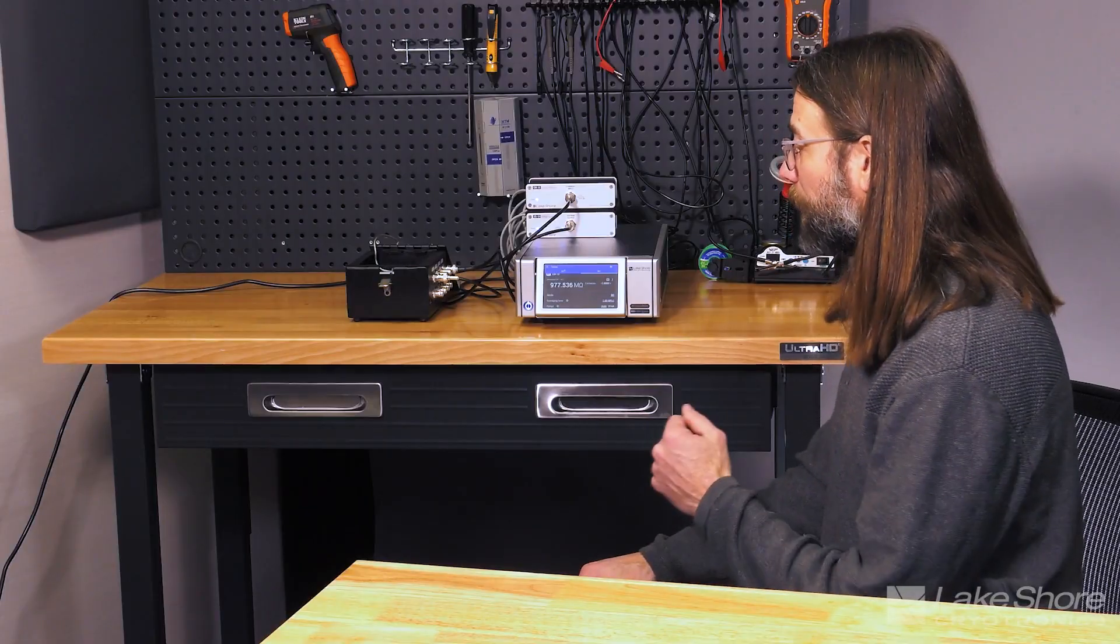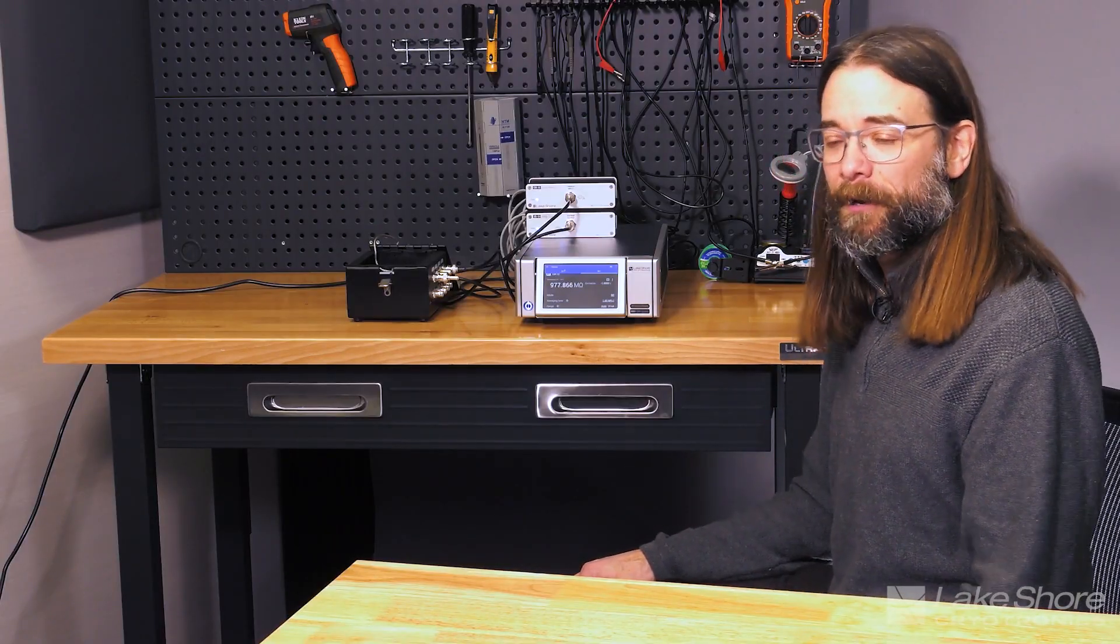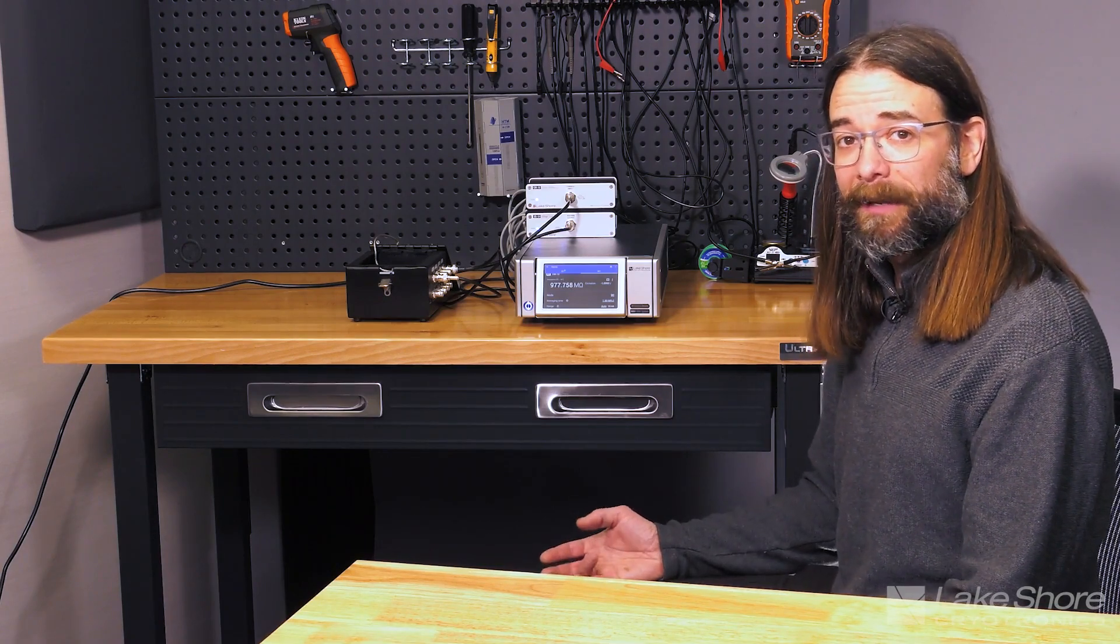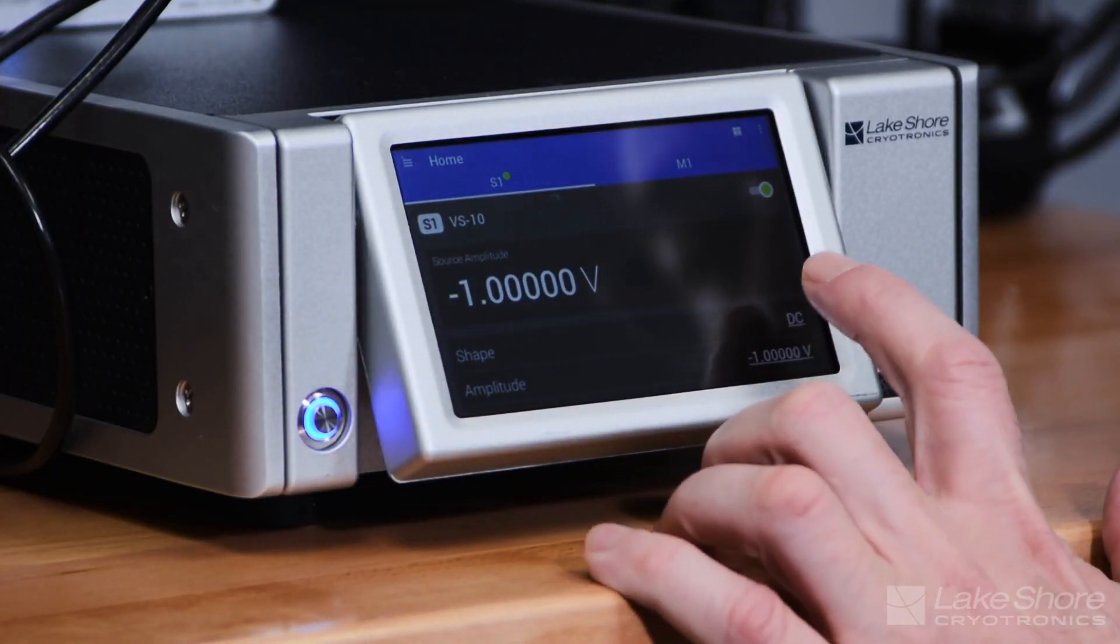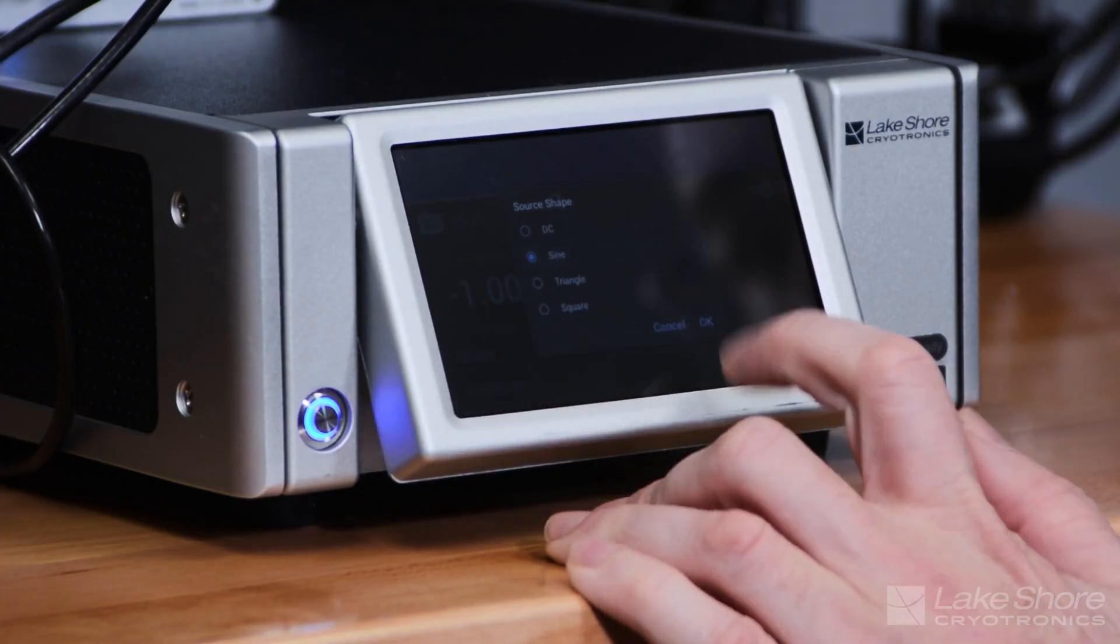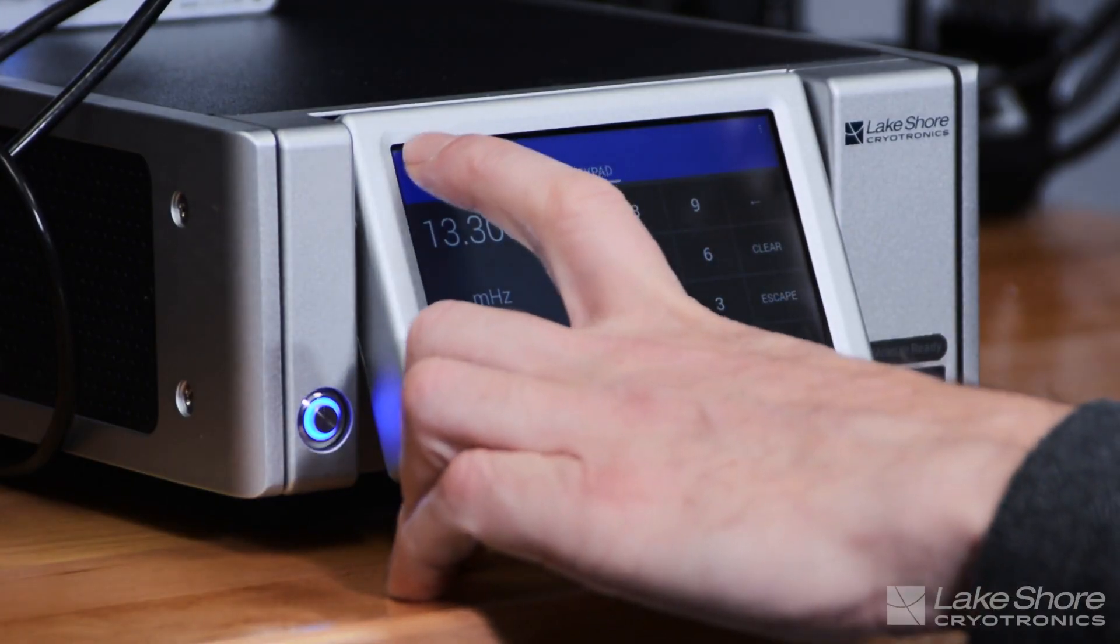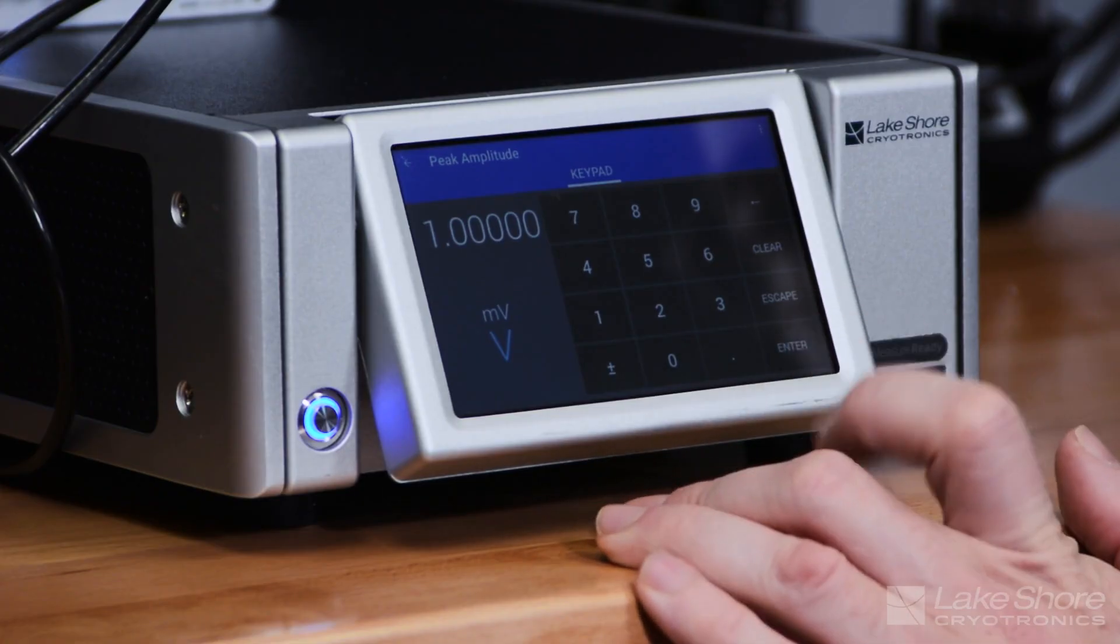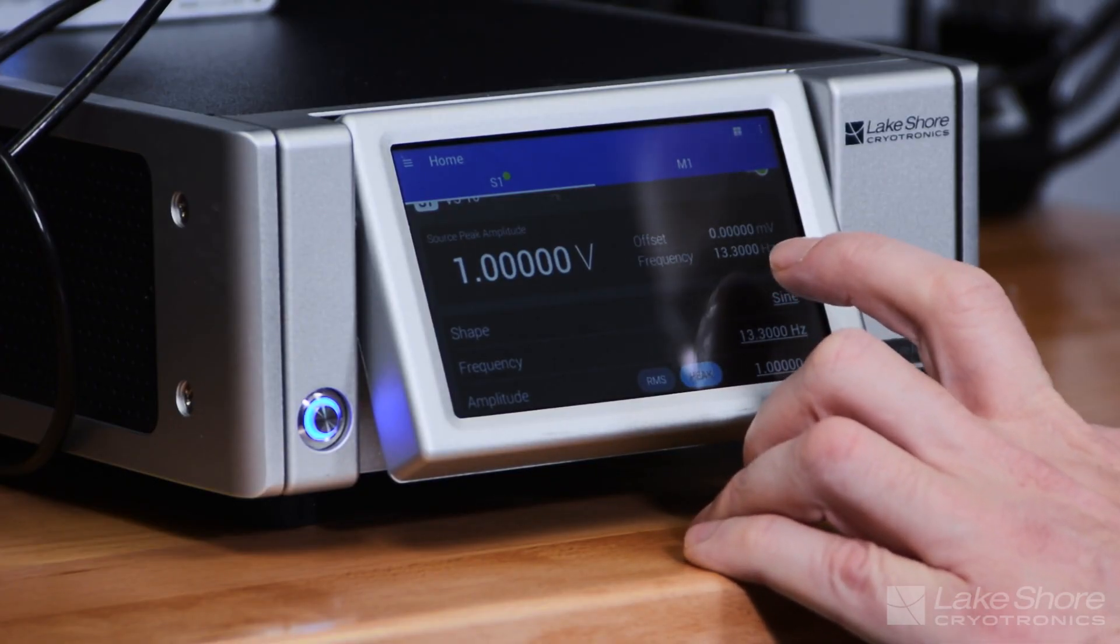So one technique that we have to getting rid of or not having as much influence or these offsets having as much influence over your measurement is using a lock-in technique or a lock-in amplifier technique. And in that way with the M81 we can really do this quite easily. We can go to shape and we can simply change this to sine and now I'm sourcing one volt of a sine wave at 13.3 hertz.